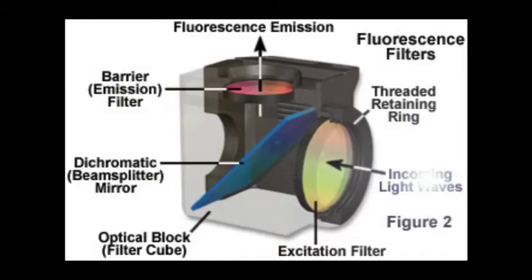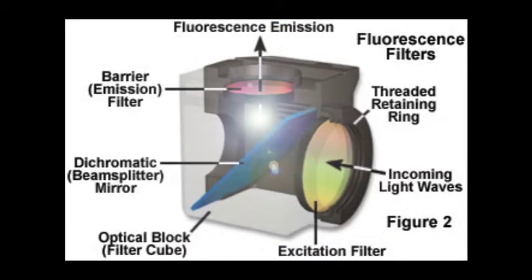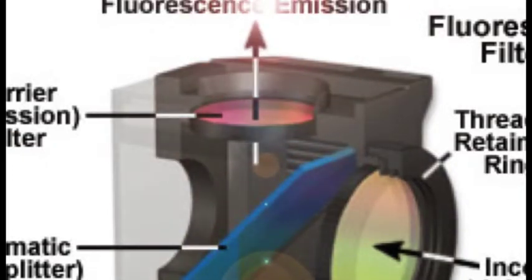And so that's going to travel from below and come through this dichroic mirror. So light coming in hits the dichroic mirror and is reflected down. Emission light comes from the specimen, passes through the dichroic mirror, and then passes through a barrier filter. The barrier filter is going to restrict the emission light to the actual wavelengths that we want to see. So the filter package is a very important part of the fluorescent microscope.